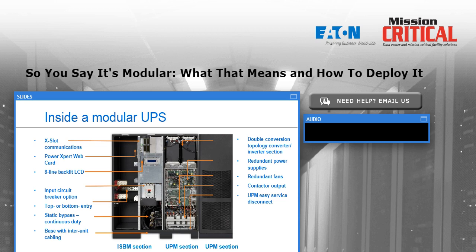And each of the 2 UPMs that you see on this UPS are identical. Each one has its own individual and separate controls. They do not depend on each other or on anything in the ISBM section in order to function. We want them to be completely independent and independently controlled so that there's no chance for a failing module to pull down the rest of the system, which is not suffering a failure and could potentially remain online, thus providing the N+1 redundancy that we desire. So lots of things are involved both for easy serviceability and built-in redundancy.